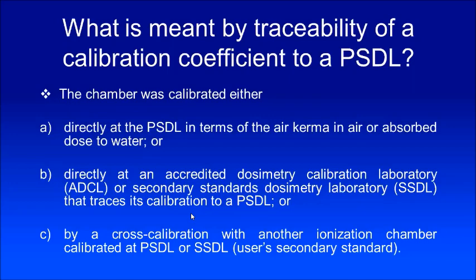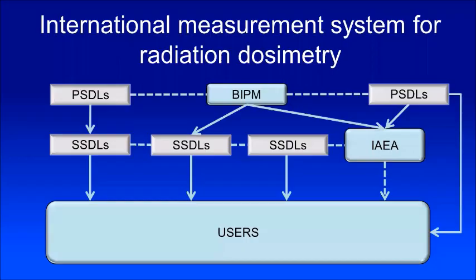Your measurement can be traced to the primary standard dosimeter. Sometimes you may use a dosimeter in your clinic which is not calibrated in a secondary or primary standard, but rather cross-calibrated in your clinic with another ion chamber that is calibrated to a primary or secondary standard. In that case, your traceability goes from your chamber to your calibrated chamber, then to the PSDL and/or SSDL. If you measure with an ion chamber with a calibration factor, that should be traceable to a primary standard.